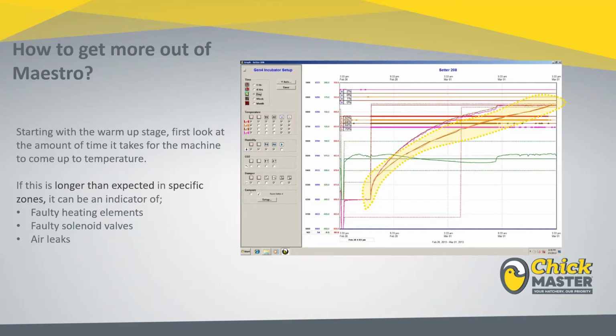So in other words, the machine is trying to heat up using an electric heat only, but we may find a chilled water solenoid that is not shutting off completely. And so we may have a little bit of chilled water leaking into the cooling coil, causing an extended period for warm up. And then oftentimes you'll see air leaks specific to that zone where the damper may be out of calibration, or the damper itself for that particular zone may have become dislodged or disconnected from the main damper actuator, and therefore is bleeding air into that specific zone. So it's relatively common when troubleshooting startup or this warm-up stage to see a zonal effect.